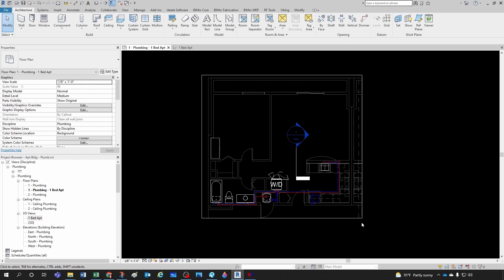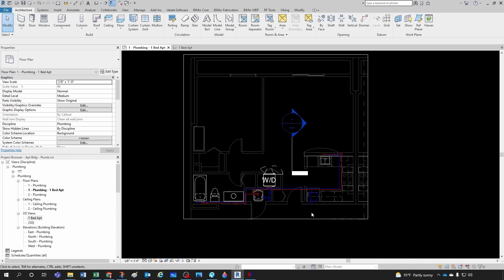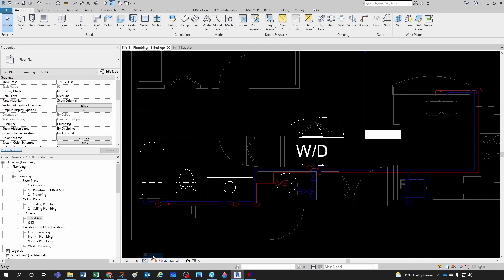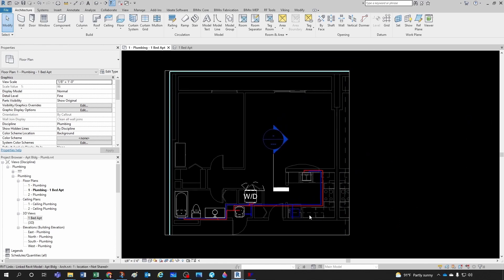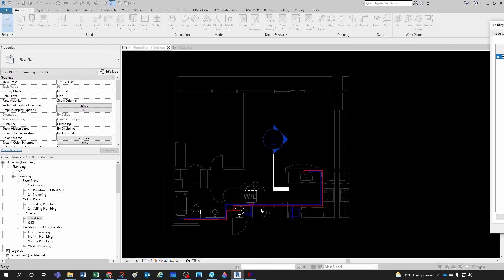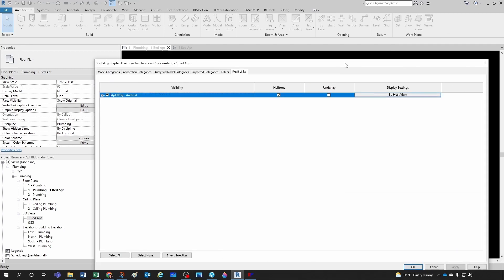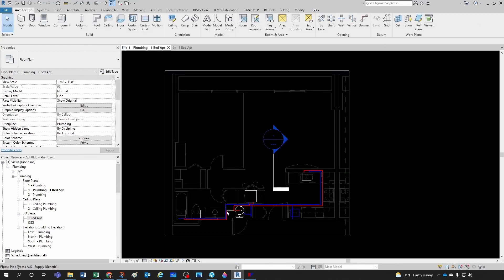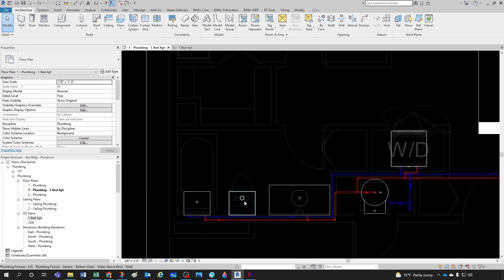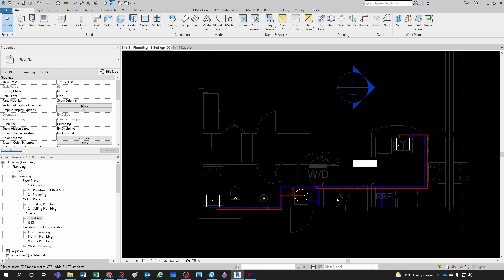Let's pipe some sanitary drainage. There's not one specific correct way of doing this — a thousand ways of skinning a cat. I'll show you a couple of workflows I like. First, I prefer to keep the display in fine rather than medium or coarse. I also go to visibility graphics overrides with VG and keep my background halftone, which takes a little relevance away from the architectural background. I keep the underlay on to see things underneath, and I keep graphic display options on wireframe so I can see connectors and align better.